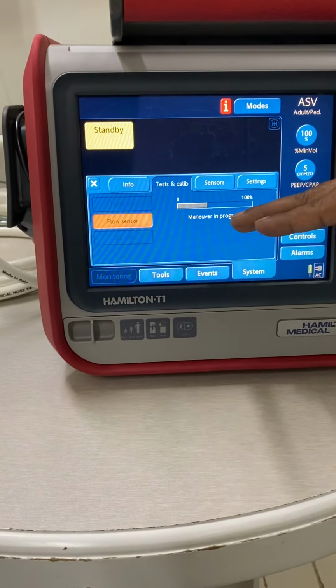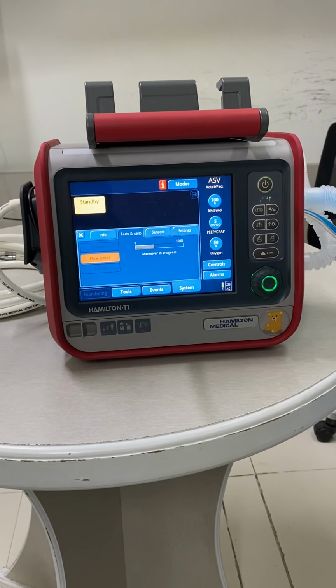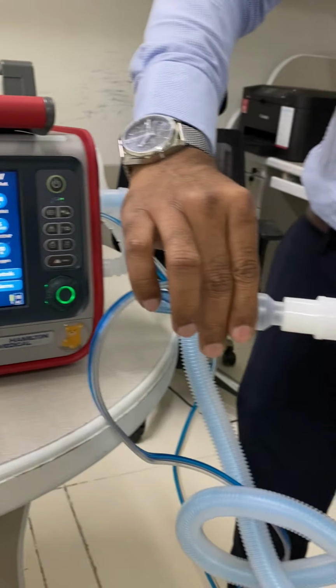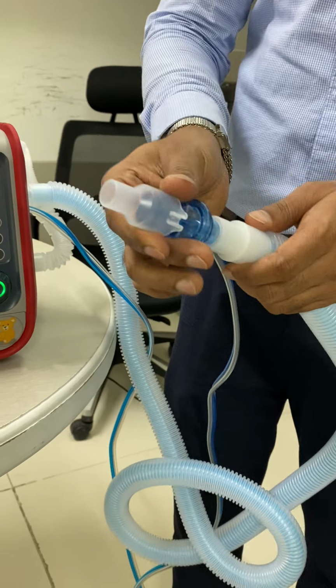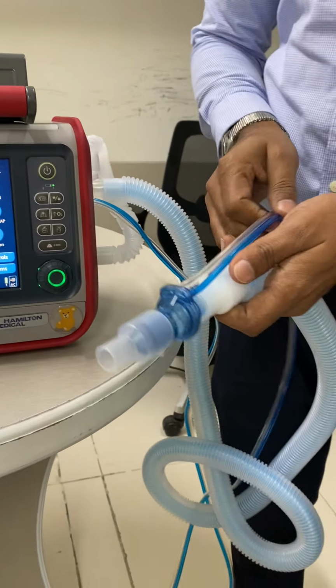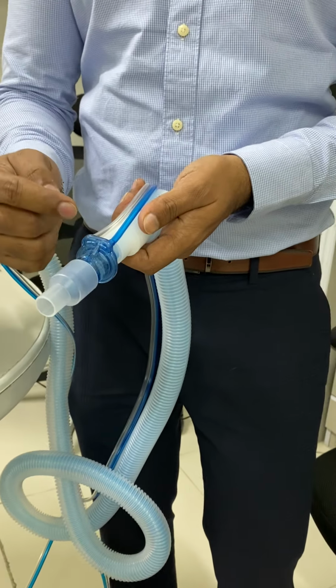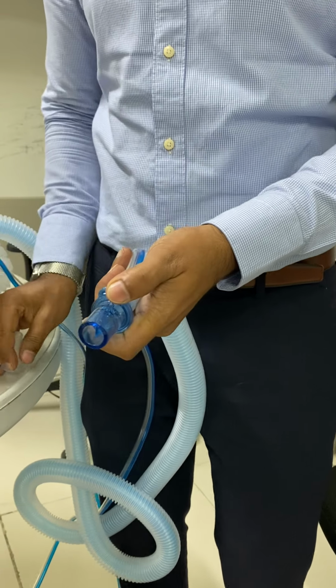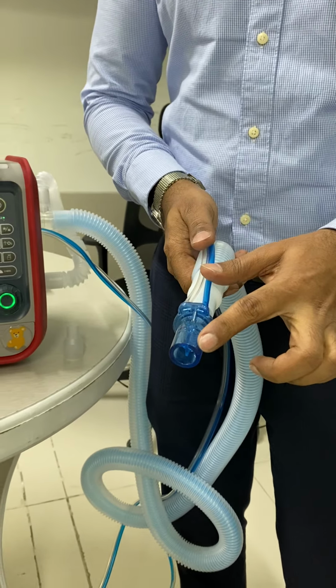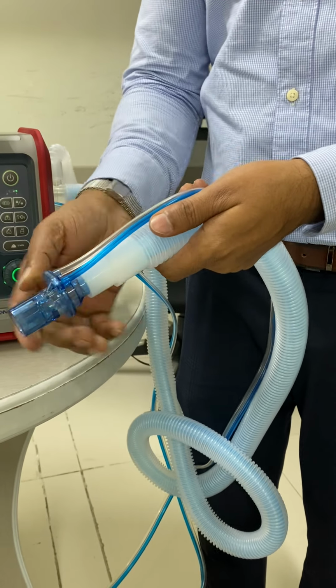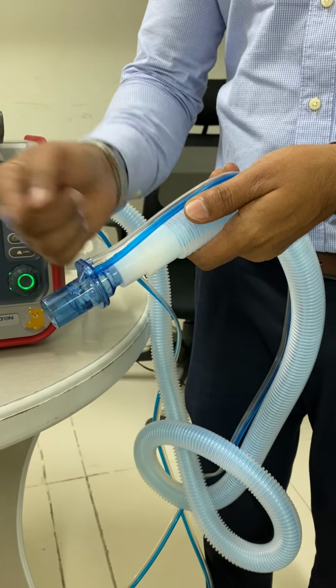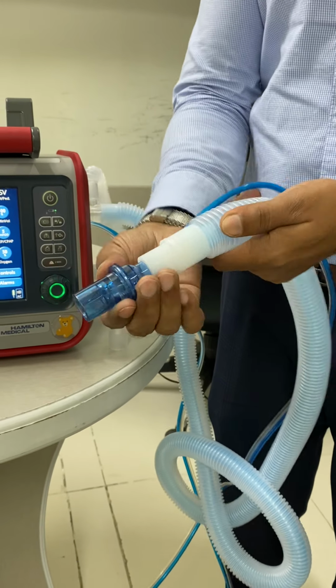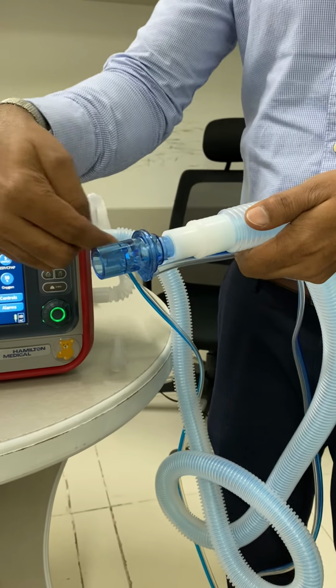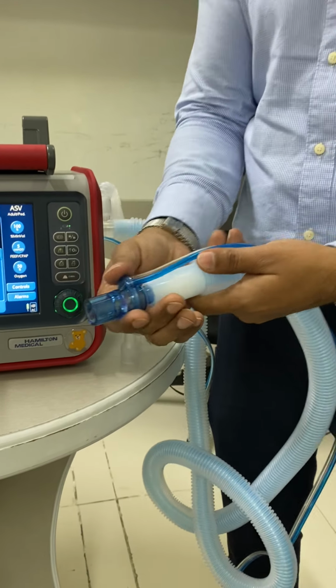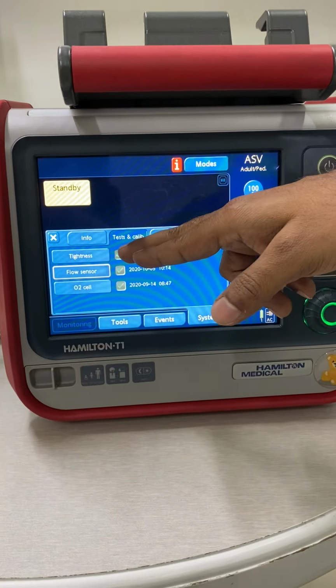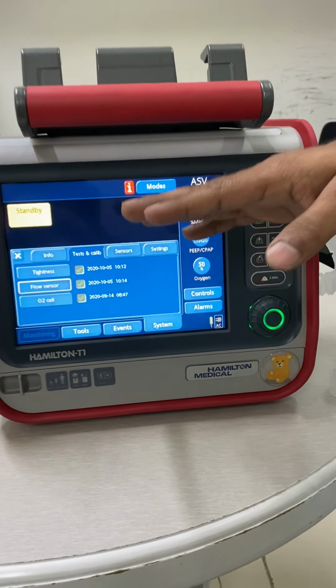And follow the instruction from here, maneuver in progress, and turn the flow sensor. You remove it and connect it in the normal way. So the normal position of the flow sensor is connecting the flow sensor without the adapter in the Y. This is the normal positioning. When you're connecting to the patient, make sure that the small tubing comes in an upright position. If it is down, secretions may go in and clog the flow sensor. Okay, so it's passed now. So we have done the tightness and flow sensor check. It's passed and the time and date is given.